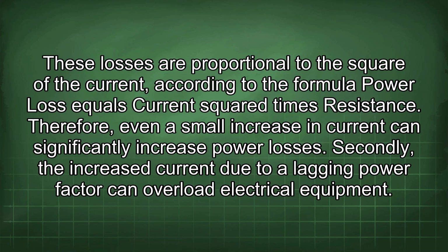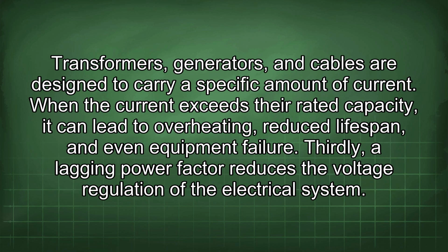Secondly, the increased current due to a lagging power factor can overload electrical equipment. Transformers, generators, and cables are designed to carry a specific amount of current. When the current exceeds their rated capacity, it can lead to overheating, reduced lifespan, and even equipment failure.